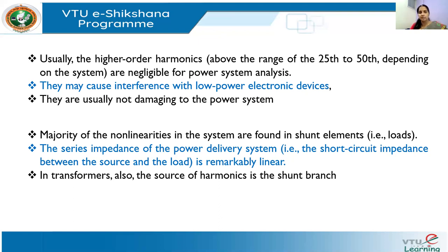In transformers, the shunt element is the magnetizing reactance, which can also be a source of harmonics. Therefore, we can conclude that the main sources of harmonic distortion are the shunt elements in the power system — whether it is a non-linear load or the shunt magnetizing reactance of a transformer. Most harmonics in the system are produced by the end-user loads.